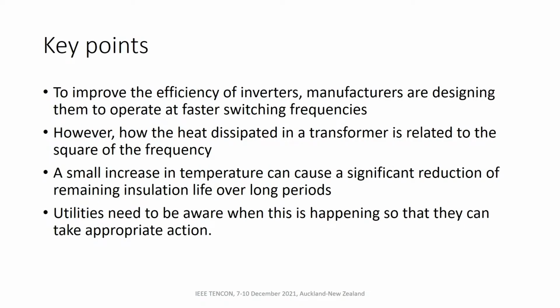Other points we've seen happening is, one thing is the inverters. They have a particular switching frequency, and, as I'll show in this presentation, we have noted harmonics coming out at the switching frequency of devices. What we can see actually happening in manufacturing right now is that switching frequencies are generally increasing, and the manufacturers are doing that partly to increase their efficiency.